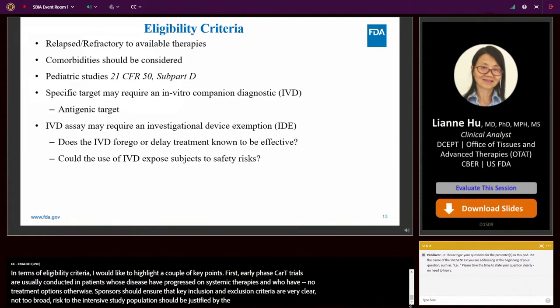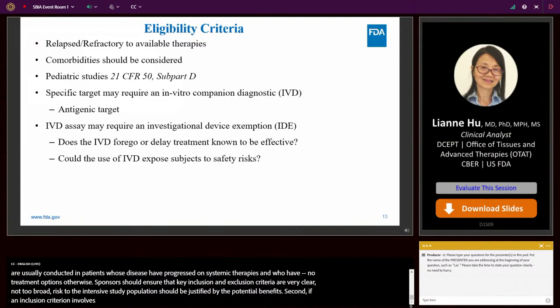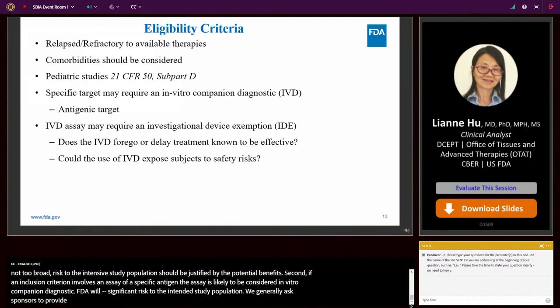Second, if an inclusion criterion involves an assay of a specific antigen, the assay is likely to be considered an in vitro companion diagnostic. In this case, the FDA will assess whether the in vitro diagnostic poses a significant risk to the intended study population. We generally ask sponsors to provide an initial assessment of significant risk or non-significant risk and submit it along with their IND application.